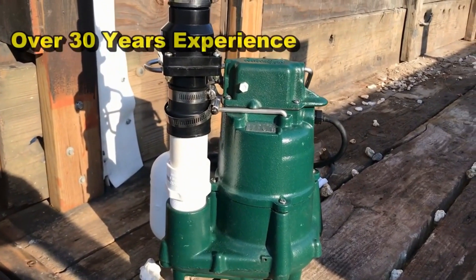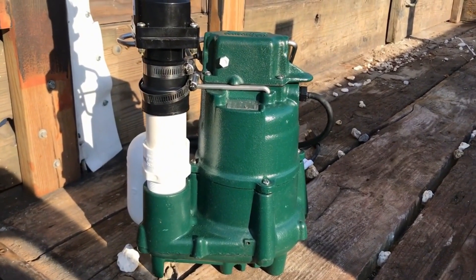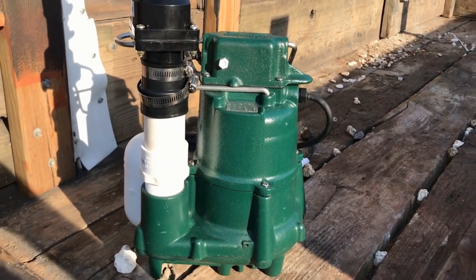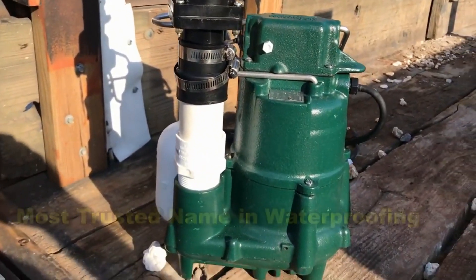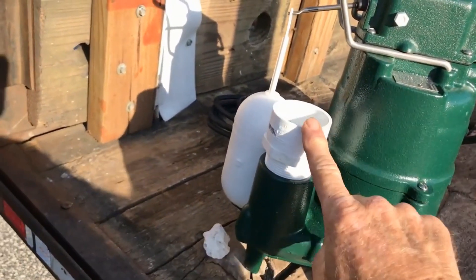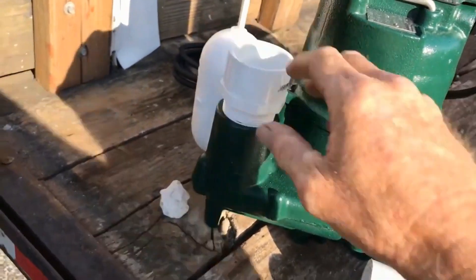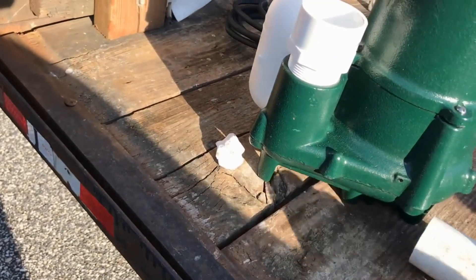One of the first things we do is set up the sump pump for the install. This is a Zoeller M98 — a half horsepower pump. It's what we call a grinder and effluent pump, capable of grinding up solids down in your basin — up to a half-inch solid — and pushing that right through the line. You start by putting a male threaded inch-and-a-half adapter; it screws into the port — just as tight as you can with your hand. Next we need a small riser just to get the check valve up above that bar.